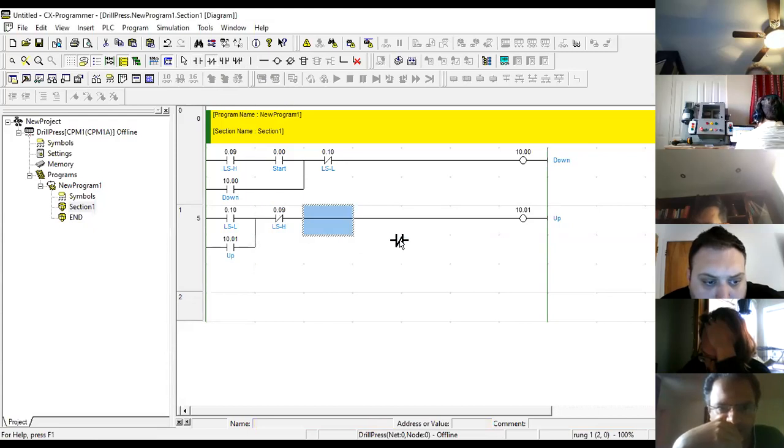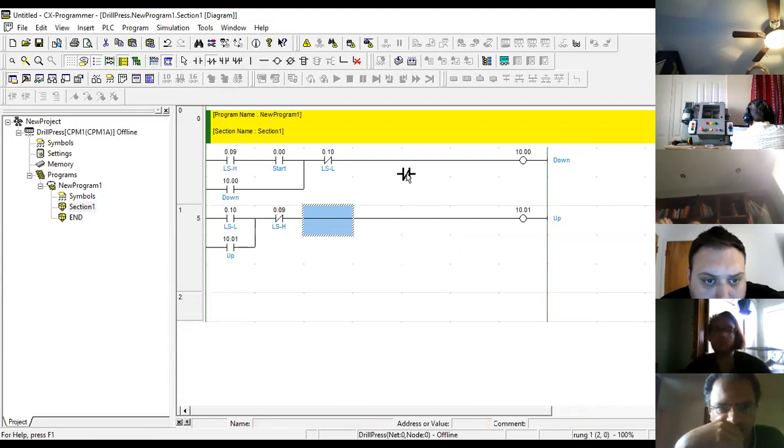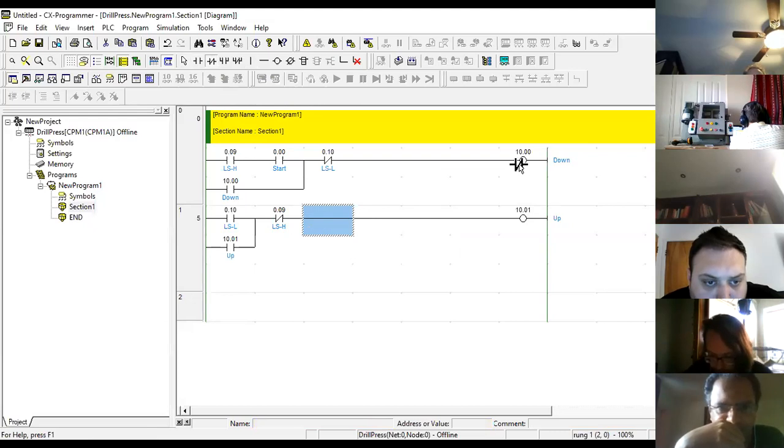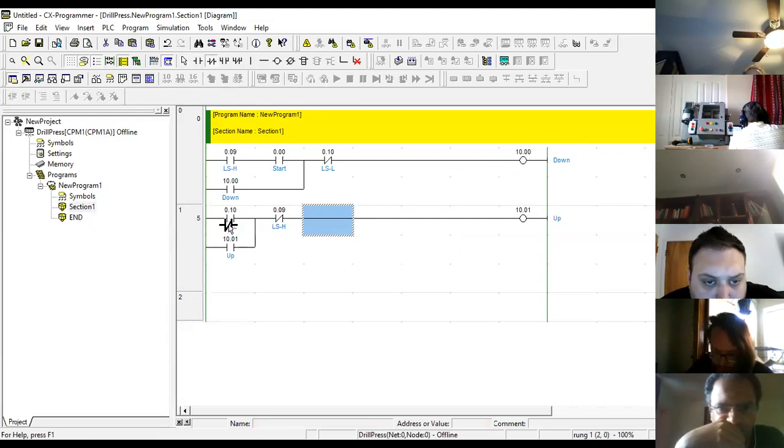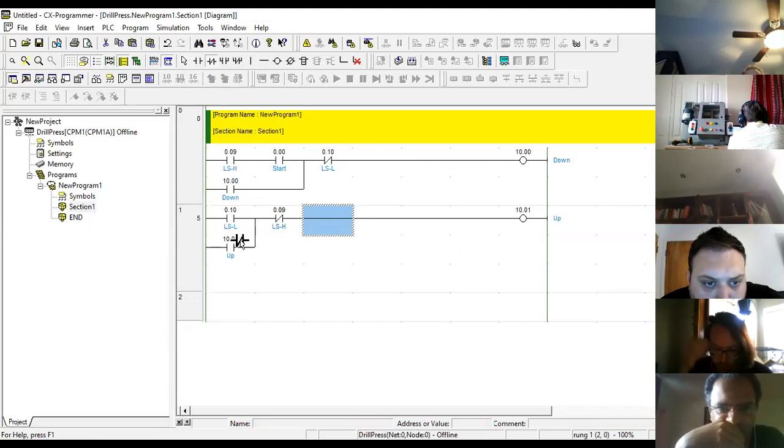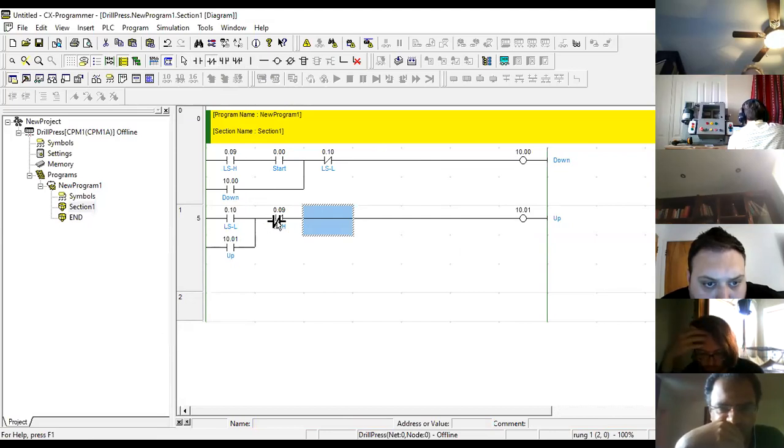So right now, what have I done? Limit switch high, the very beginning plus start activates an output. This output is linked to my motor going down. If my motor is going down, it's going to eventually hit the limit switch low. When it hits the limit switch low, I'm going to deactivate my down. I'm going to activate my up, which maintains. Now it's going up. When it hits the upper limit switch, it stops.